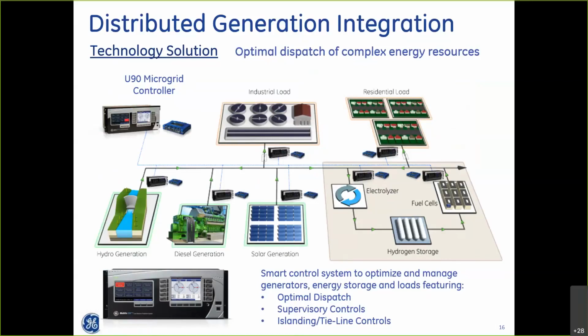So we took a microprocessor-based relay and made it into a microgrid controller by adding logic to it. It would make sure the load was satisfied all the time, but optimize the use of the fuel cells, the solar generation, and the hydro generation, and minimize the use of the diesel generation.